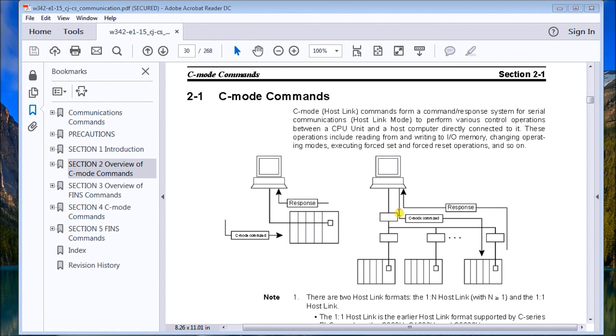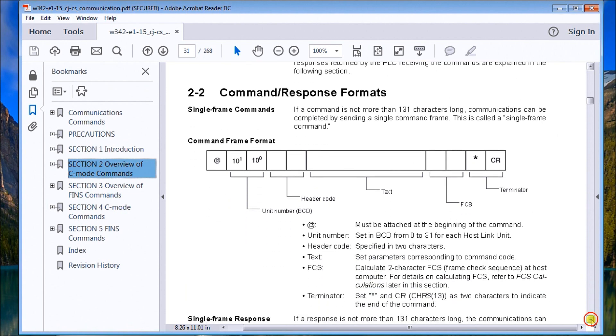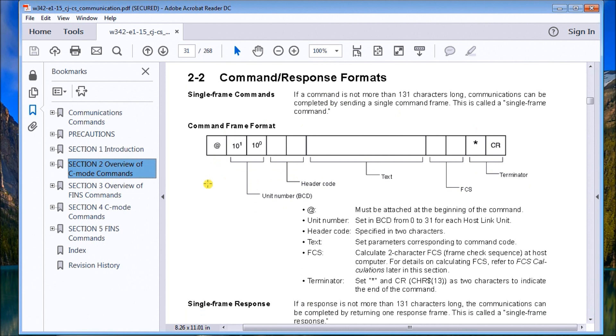We're going to use Visual Basic .NET to open a serial port, talk to the controller, get the response back, and display that information. Looking at the command structure: all communication starts with an at sign, then we have the unit number in BCD — 00 to 31, giving us 32 devices. We have a header code which is our command code; in our case we're reading data memory, so that's RD. The text that follows relates to the command code.